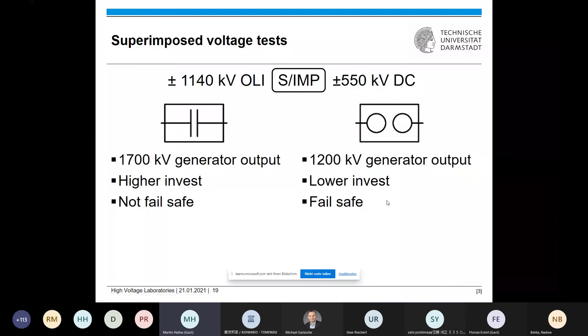And also one argument which is quite important when you make such a big test. The highest voltage in your overall circuit when you use a coupling capacitor is 1700 kV. The highest voltage in your overall circuit for spark gap testing is 1200 kV. So if something fails in your test assembly, your device under test will get here for a spark gap only 1200, and here it could be maximum 1700. So you see a spark gap is fail safe while a coupling capacitor is not fail safe. For us, these were main arguments to say, okay, we will go the way with the spark gap, and so we decided to use the spark gap.